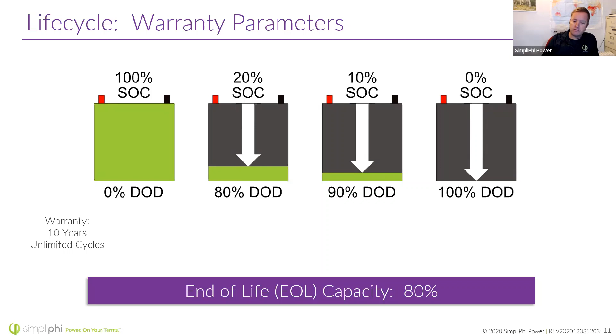That said, you can discharge them to 100%. If you're cycling these daily, using them in an off-grid situation or for time-of-use arbitrage, we recommend an 80% planned depth of discharge. That gives your customer the most life from the battery after the warranty period's done. If you're simply in a backup situation, or not really cycling the batteries much, go ahead and size for 100% depth of discharge. We have other trainings, both upcoming live trainings and pre-recorded ones on our YouTube channel, that go deeper into how to size these systems based on depth of discharge, so check them out.